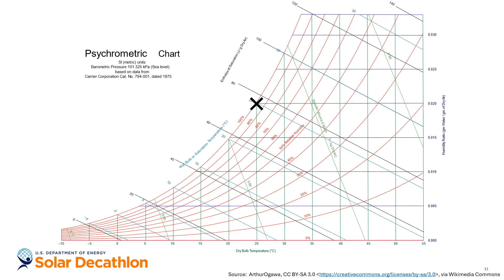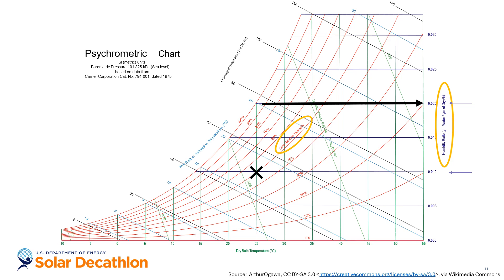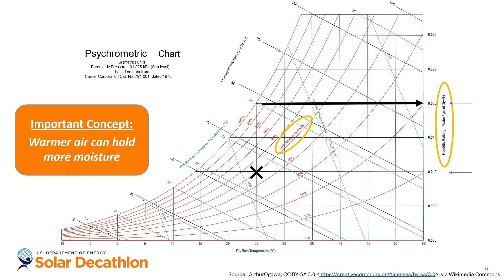We can also determine how much water vapor is actually in the air at the saturation point. Looking horizontally to the right at the y-axis, we find the absolute humidity or humidity ratio expressed as a mass ratio of water to air. At the point we've plotted, this value is approximately 0.020 grams of water per gram of dry air. At 50% relative humidity, the humidity ratio is cut in half to 0.010. As dry bulb temperature increases, the amount of water vapor that can be present also increases — basically, warmer air can hold more moisture. This is one of the most important concepts in this episode.